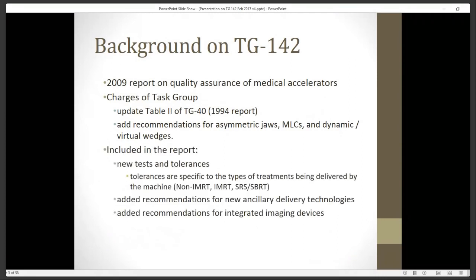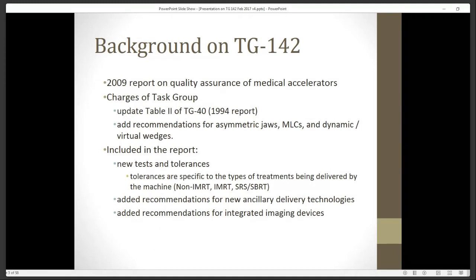What the actual report includes is not only added recommendations for asymmetric jaws, MLCs, and virtual wedges, but also integrated imaging, and it gives some new tests and tolerances. One of the big differences is that these tolerances are now specific to the types of treatments being delivered for the machine, whereas TG40 gave one-size-fits-all recommendations for any linear accelerator. Now it's broken down into non-IMRT, IMRT, and SRS/SBRT linear accelerators.